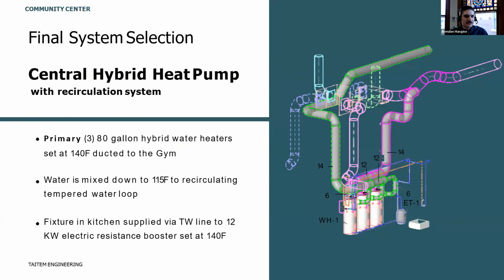So this is the system, right? It's 3 hybrid water heaters, and we're ganging these together and ducting the supply and exhaust of these hybrid water heaters to a gym space next door to where the domestic hot water plant is. There's also a large commercial kitchen, and the way we're addressing this is that we are adding a booster heater. So we're sending a tempered water loop at a lower temperature than normal because scalding is a risk here. And then we're going to boost to 140°F at the commercial kitchen. That's just with an electric resistance tankless water heater, and it is sized to completely deliver hot water at 140 degrees to all the critical loads to keep the kitchen in health code compliance at all times, even if we deplete all the hot water in the project.